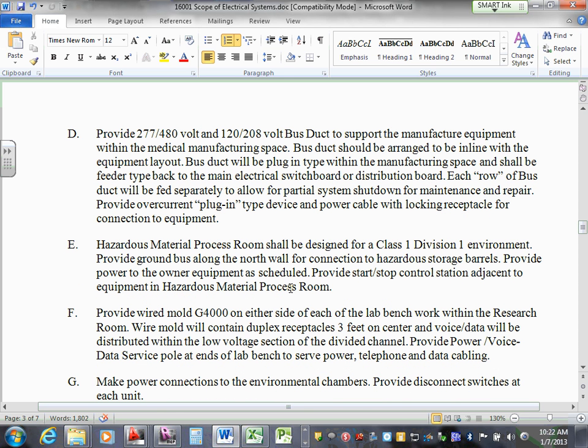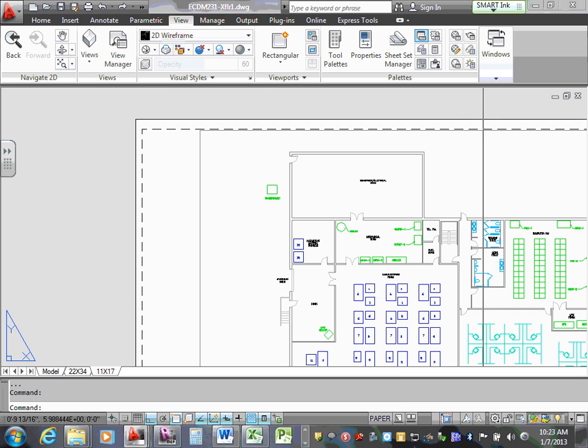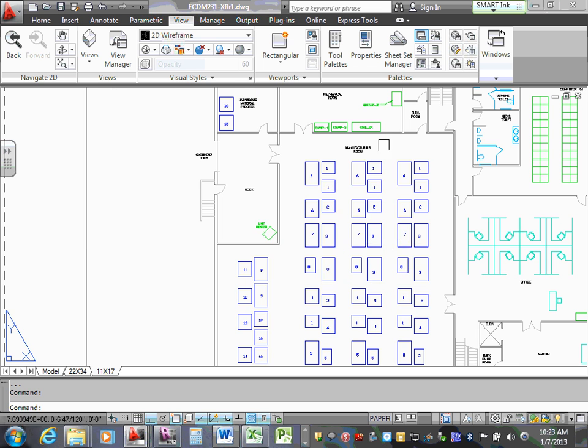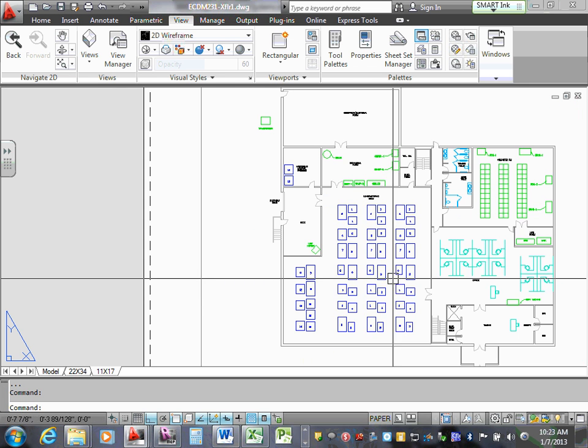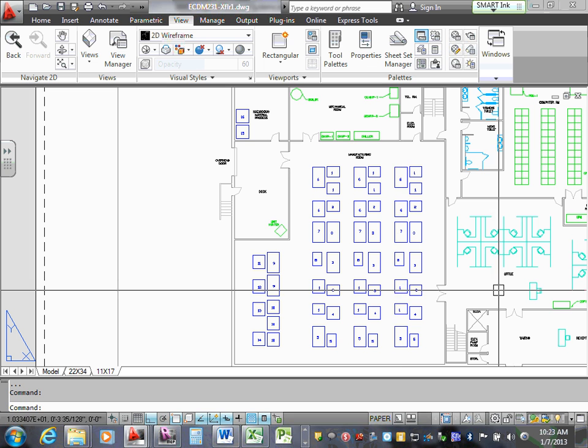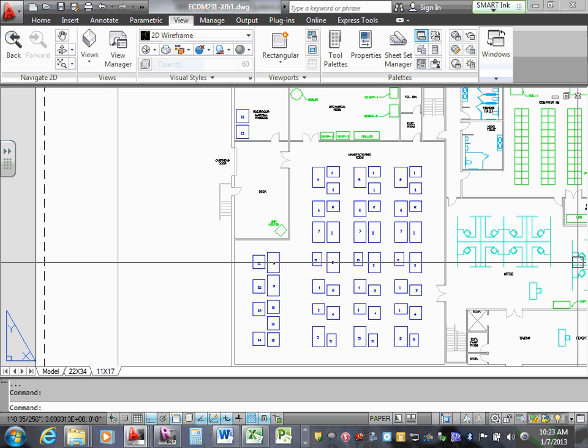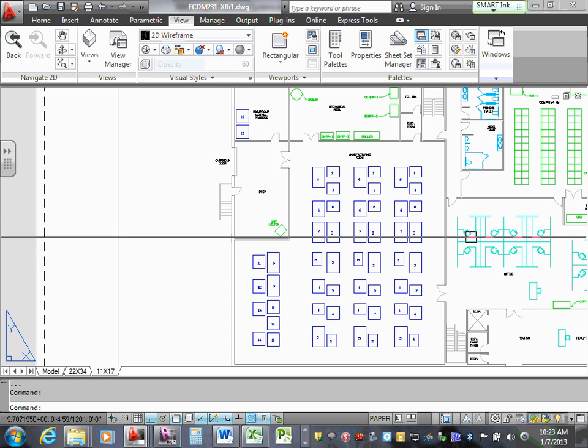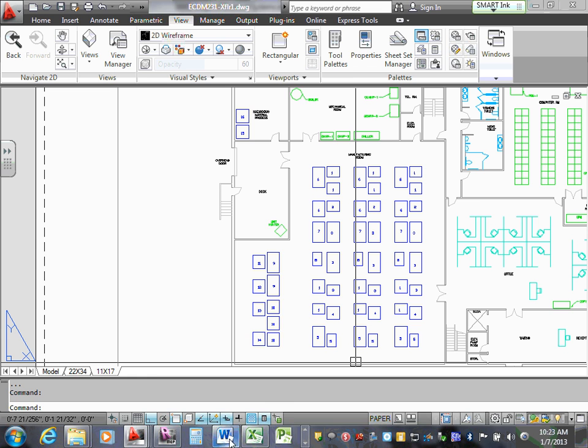On page 4, as a comment, and as I mentioned on the plan overview, there's bus duct. We still think that's probably the most cost-effective way to distribute power down to the equipment below. I'd anticipate the equipment here, just like at the other facility, does change—things come and go, processes change for those folks. So the bus duct gives them a lot of flexibility to change out equipment on the fly, reconfigure, or make it higher or lower as needed. So bus duct is a good solution, we think, to feed it.